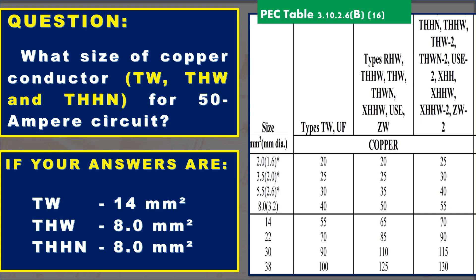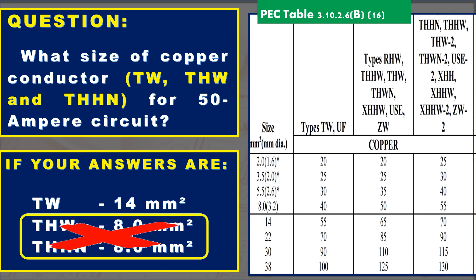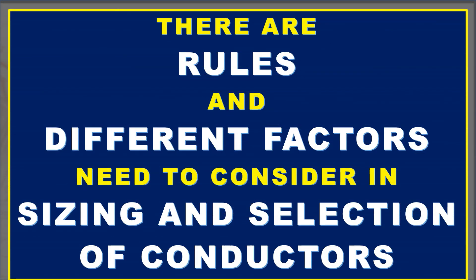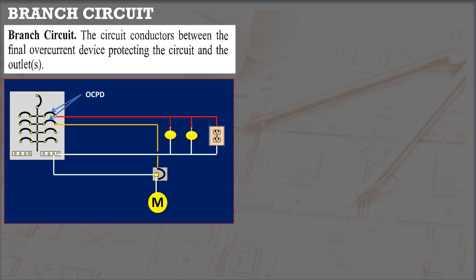Let's go back to the earlier question — why is 8 squared millimeters THW and THHN not correct? In selecting and sizing conductors, there are rules and different factors to consider. A safe electrical system starts from the very basic wiring fundamentals: the branch circuit. In code definition, a branch circuit consists of the circuit conductors between the final overcurrent device protecting the circuit and the outlets. It could be a non-motor load such as lighting, receptacle outlets, water heaters, etc., or a motor load circuit.